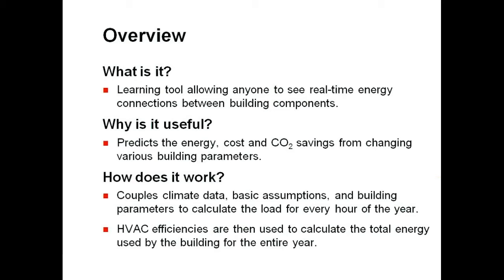The calculator itself predicts the energy, cost, and CO2 savings associated with changing the parameters of a building's design. The calculator works by coupling location-specific climate data — such as what the temperature is outside — a few simplified assumptions, which are all listed on the website, and the listed design inputs to calculate the building's load for every hour of the year. The HVAC efficiencies are then used to calculate how much energy this load entails, and from there we use a simple equation to calculate the building's annual cost and CO2 emissions.